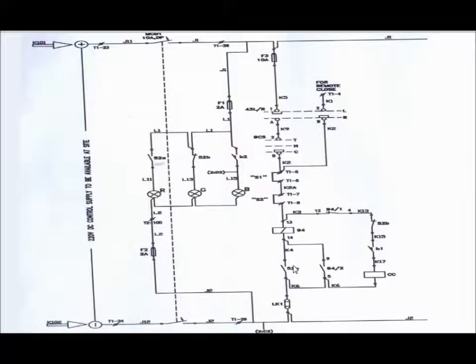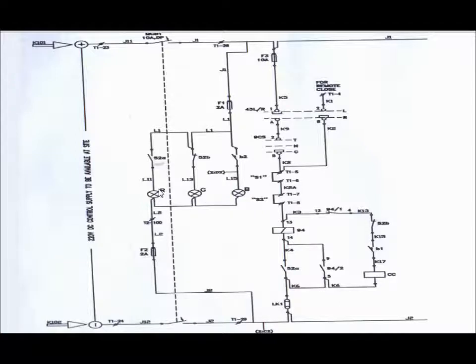As the circuit breaker turns ON, the 52A auxiliary contact will move to NC position. As the auxiliary contact is in NC position, the red light will glow, indicating the breaker is in ON condition.